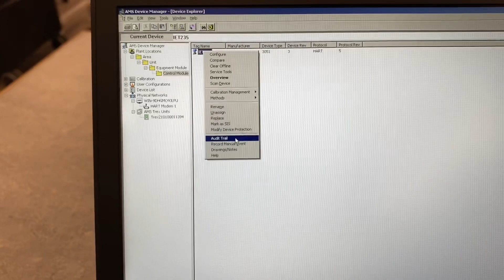After the replacement, if we wanted to add more detail, we could record a manual event to provide information on why the device was replaced. Then for reliability purposes, we could look back on all the devices to see why they were failing, the modes of failure, and get that information from the AMS database.